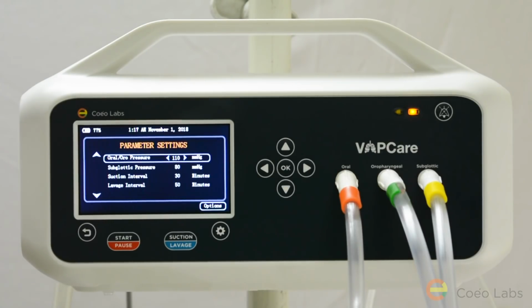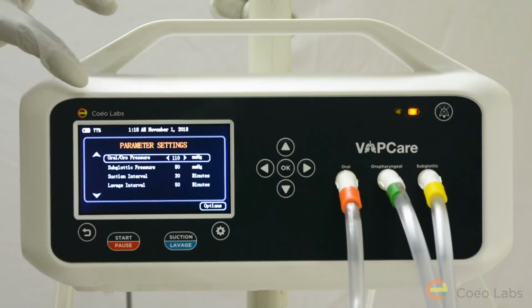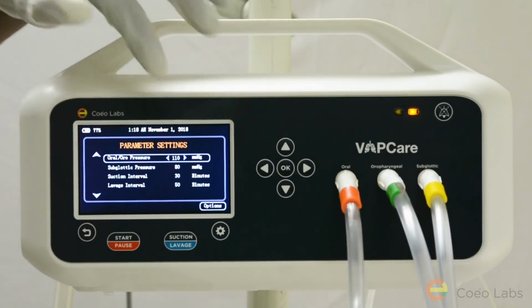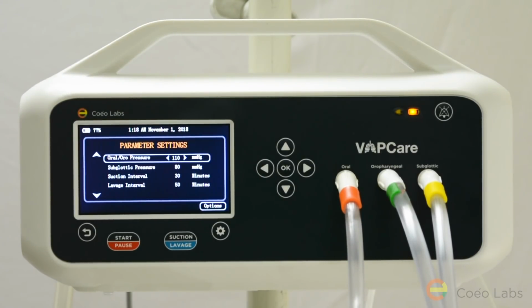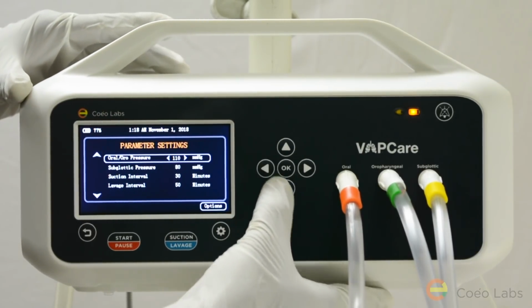Once the connections are made, the system leads to the parameter setting screen. Here the physician can choose to set the pressure in different anatomical regions. Oral and oropharyngeal pressures can be set anywhere between 45 to 200 millimeters of mercury, and subglottic pressure can be set from 45 to 120 millimeters of mercury. The suction interval can be set from 15 minutes to 420 minutes, similarly lavage interval. The default values are 110 millimeters.